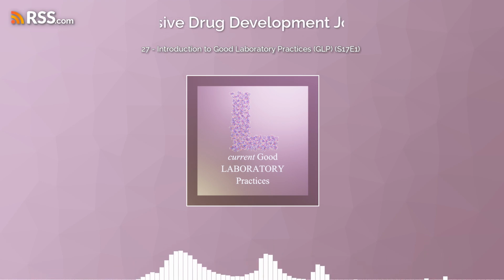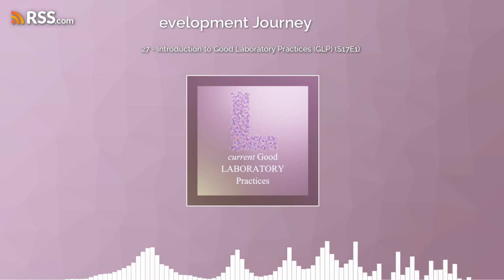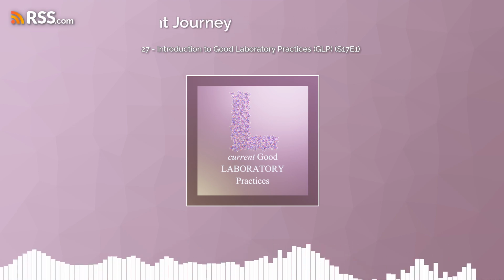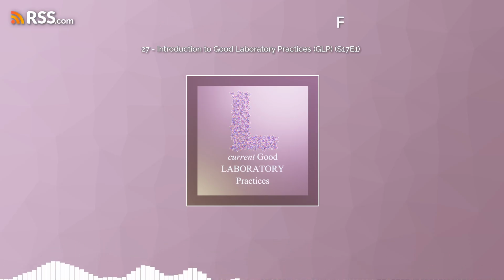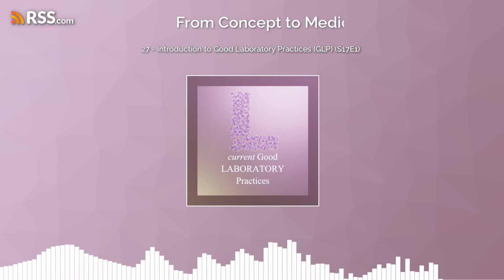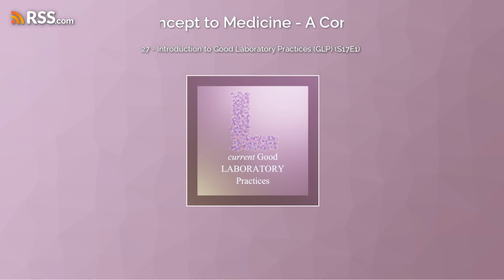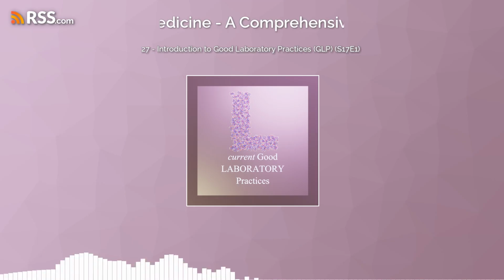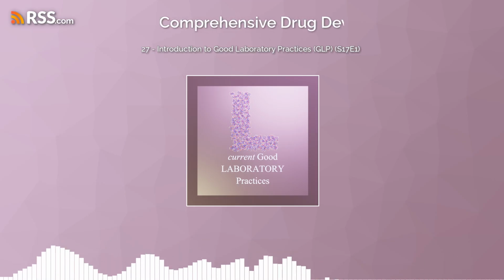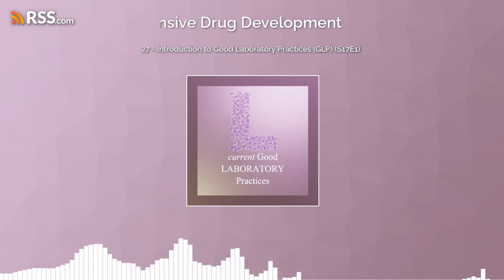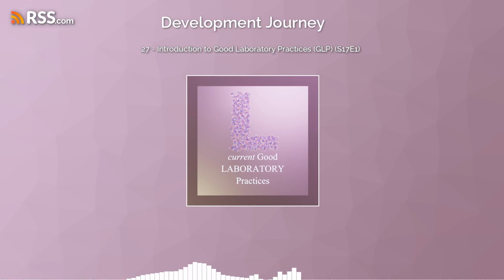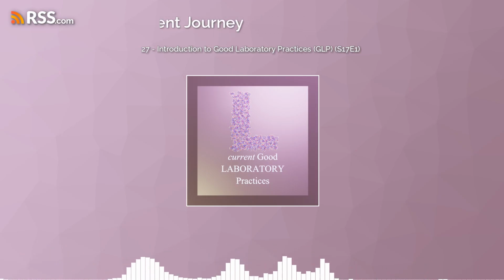I see. So it's not just about knowing how to use the equipment, it's about making sure it's performing correctly too. Right. We call that qualification, making sure it's installed correctly, that it's operating as it should, and that it's calibrated regularly for accuracy and precision. And it goes beyond the fancy equipment, too. You need SOPs for routine things like cleaning and sanitizing, even pest control for the whole facility. Because even a tiny contaminant could mess up a sensitive experiment.